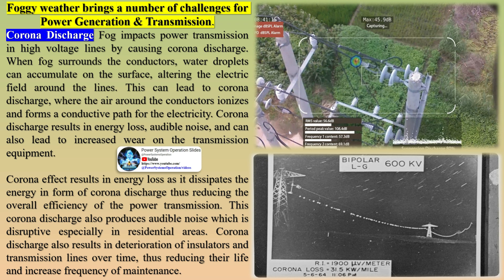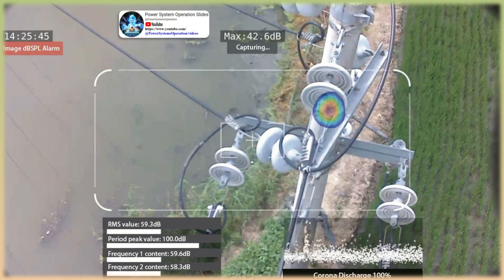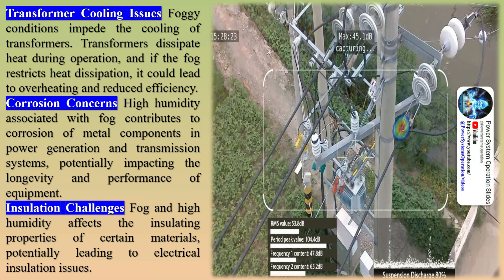Consequences of corona losses: reduced transmission efficiency — the energy loss due to corona discharge represents a portion of power not delivered to the load, reducing overall transmission efficiency. Increased operating costs — the energy loss to corona discharge needs to be compensated by generating additional power, leading to higher electricity generation and transmission costs. Corona discharge can also generate audible noise and electromagnetic interference, impacting nearby communication systems. Foggy weather brings challenges for power transmission — when fog surrounds the conductors, water droplets accumulate on the surface, altering the electric field around the lines, leading to corona discharge, energy loss, audible noise, and increased wear on transmission equipment.